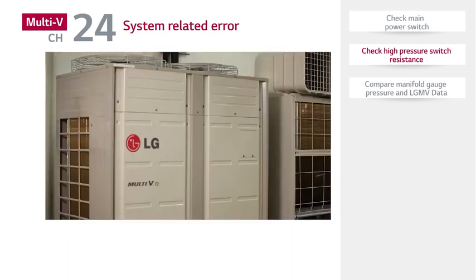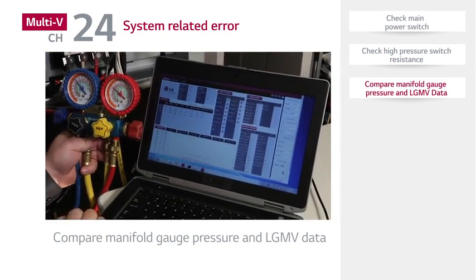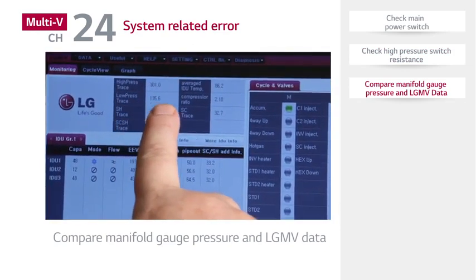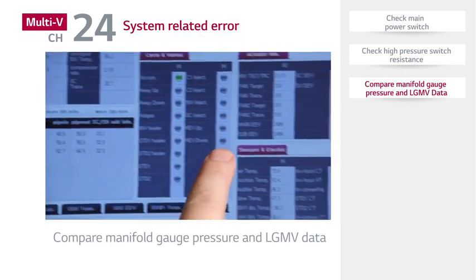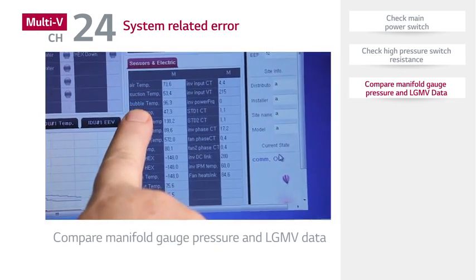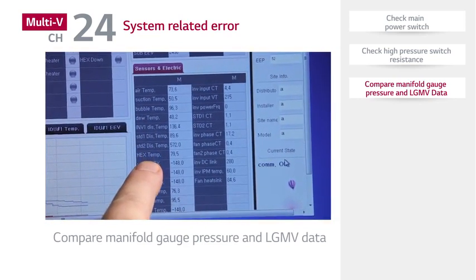Be sure to check the area around the outdoor unit to ensure that there are no environmental factors such as dirty coils, obstructed fans, etc. Check the manifold gauge pressure to compare pressure against the LGMV data. Check if pressure actually rises above the high-pressure setting of 580 PSIG. If the pressure exceeds 580 PSIG, the fan operation is normal and the coils are clean, the refrigerant charge should be reviewed for overcharge or non-condensibles.